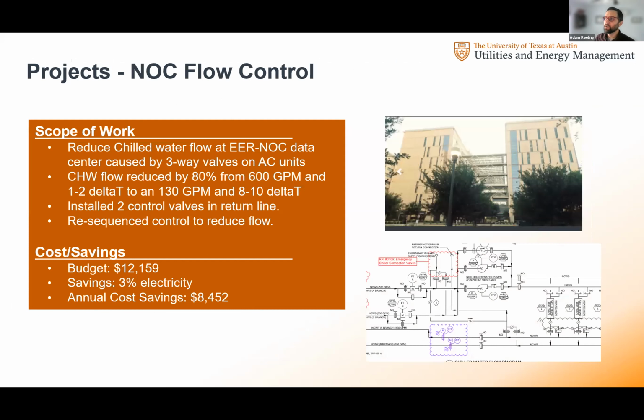Here's another project example, the NOC, a data center area in a building. Somehow 3-way valves got installed in the AC units, meaning rather than the valve stopping the chilled water from going through the unit, it just diverts it around the unit, so it doesn't control any flow at all. We were only getting 1 to 2 delta T with chilled water at this data center, which is nuts because data centers are big users—the flow was just out of control. Low delta T makes your chillers run very inefficiently, so we installed control valves and got it down to 130 and 8 to 10 delta T. That was 3% electricity savings for the building, and didn't cost very much either, only $12,000.